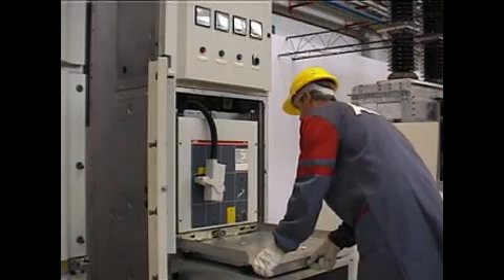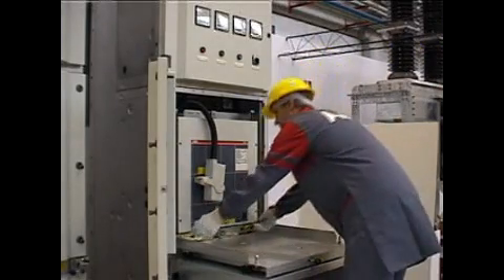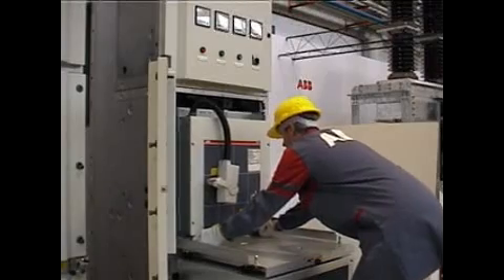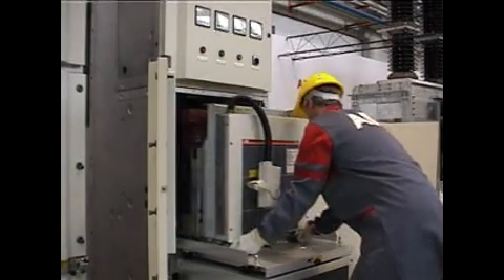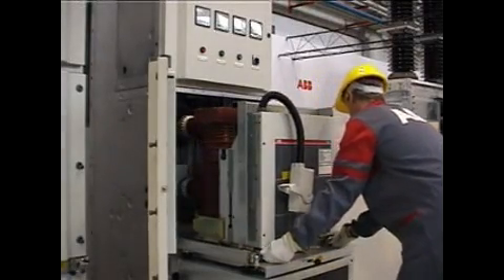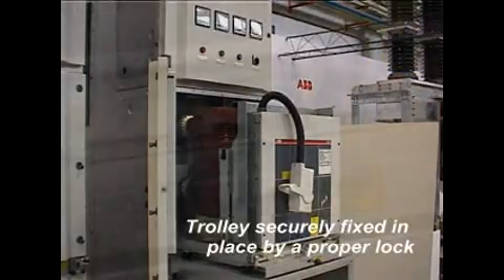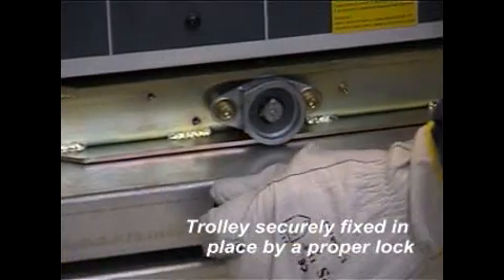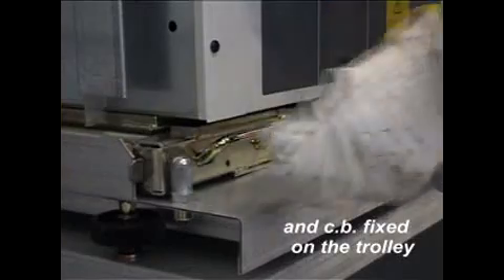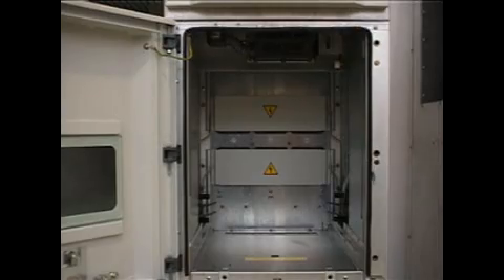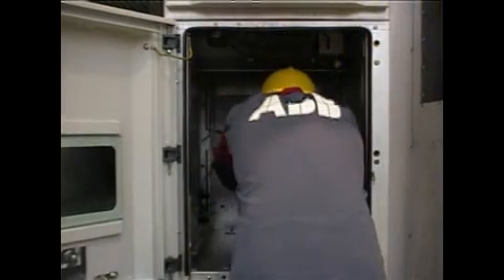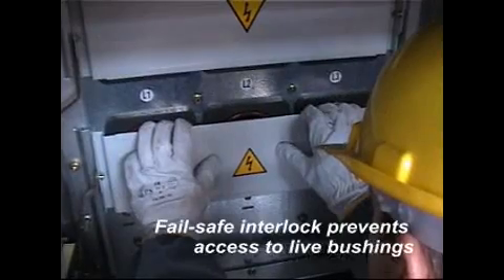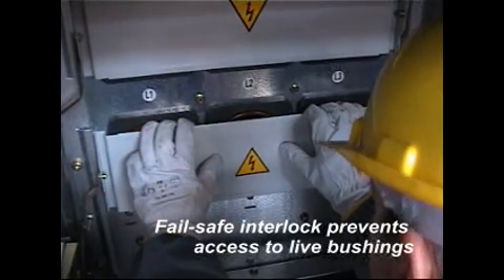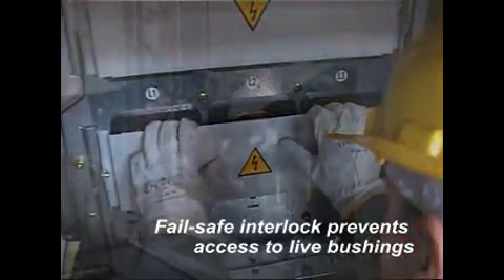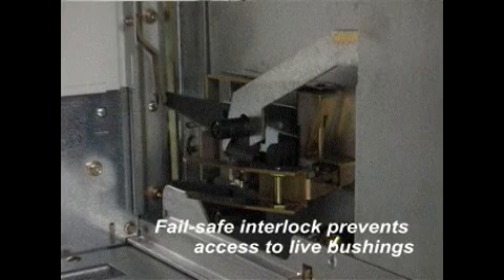If we remove the plug, the circuit breaker can be extracted from the cubicle by means of a proper trolley which can be safely secured to the panel during the travel and that is fitted with proper locks to make sure that the breaker will remain in place when the trolley is moved away. We are now showing you the fail-safe interlock which prevents the operator from getting access to the live bushings by removing shutters.